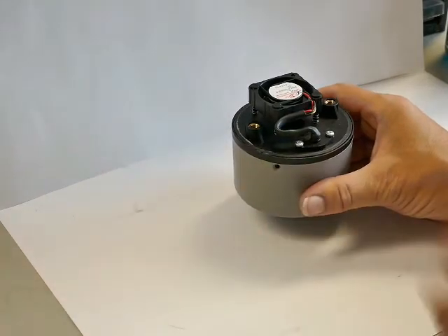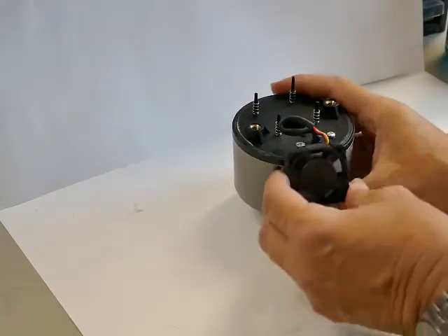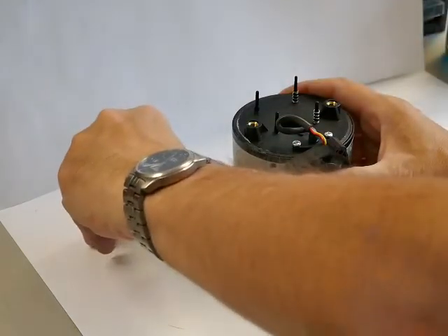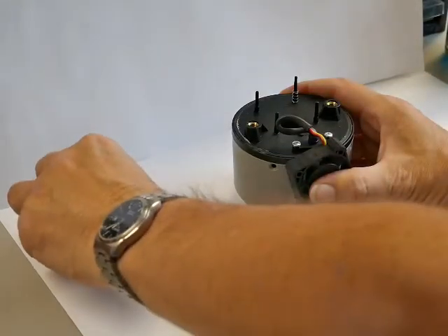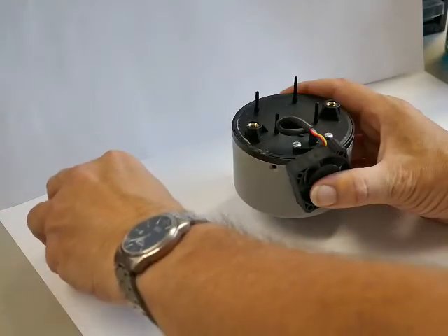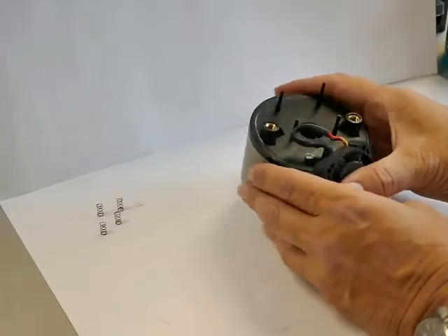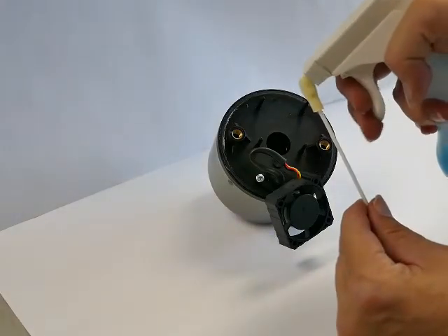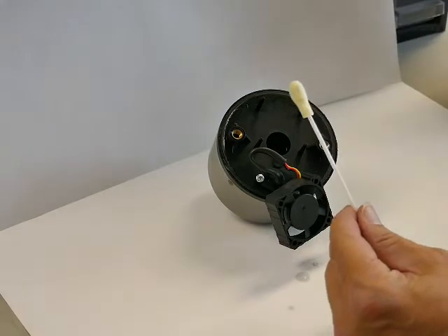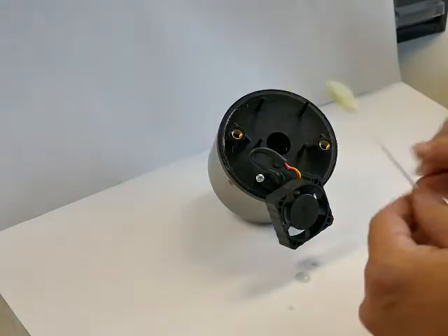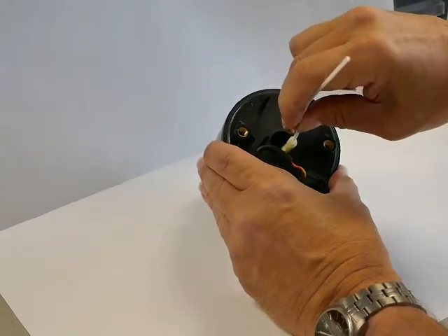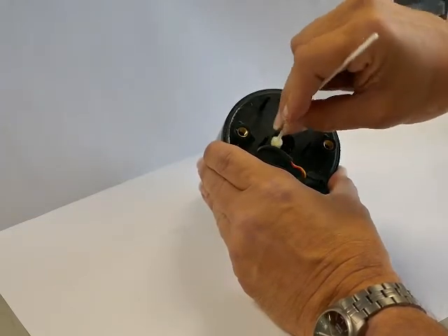Keep the retaining plug in a safe place, as it is easy to lose. Lift the fan off the pegs and remove the 4 springs. Again, keep these in a safe place. You can now see inside the sample chamber. Apply a small amount of glass cleaner to a foam bud. Insert the foam bud into the sample chamber, to clean the sides, and the small hole at the end of the chamber.